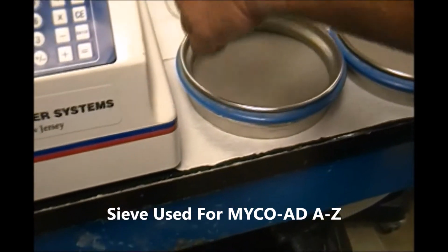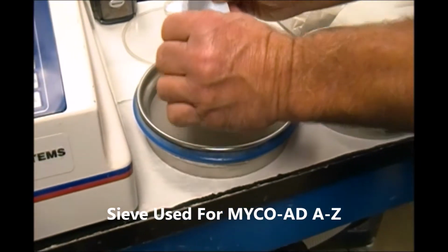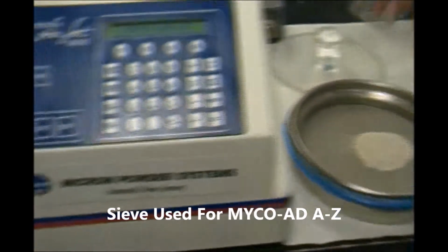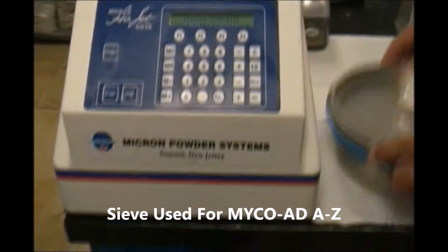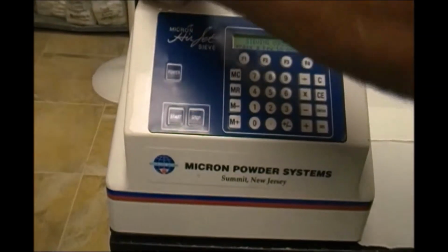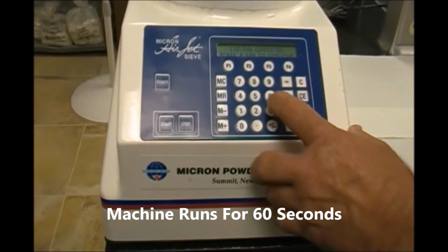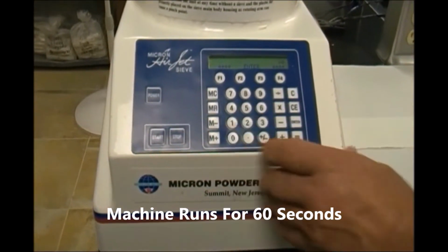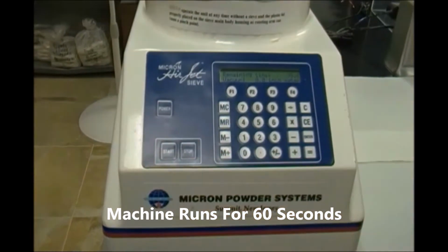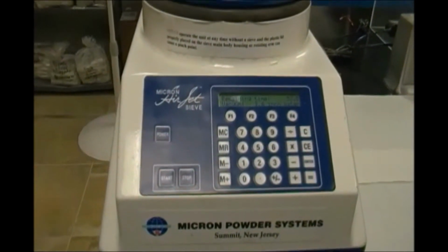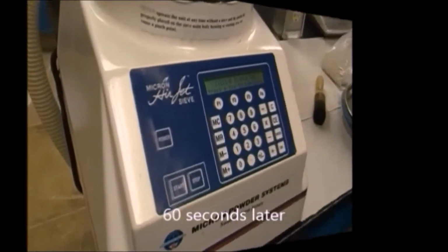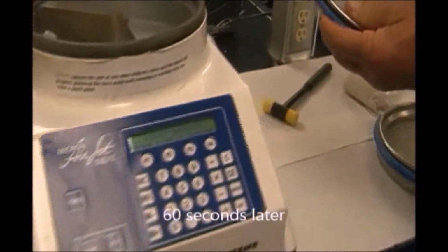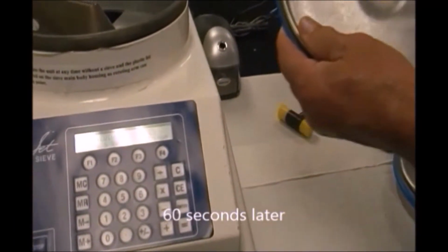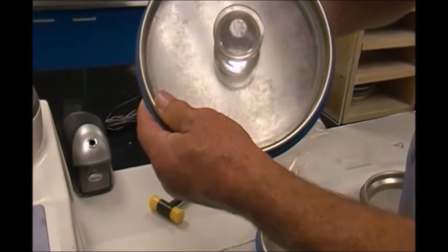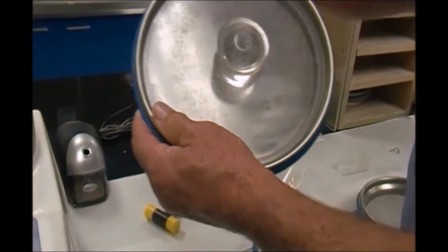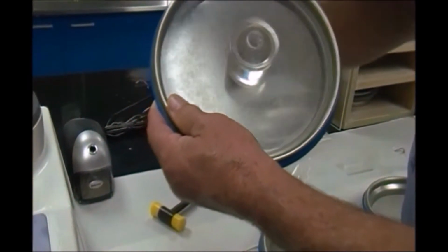Next, we will place the product into the sieve for the test. The sieve will be placed in the micron powder machine for analysis. The machine is set to run for 60 seconds. After the 60 seconds, we'll measure the residual product, which will allow us to determine what percentage of the product is of ideal particle size. After 60 seconds have passed, the sieve mesh screen will be removed from the micron powder machine. We will use a small brush along the backside to brush off any product that went through the sieve but may still be on the screen.